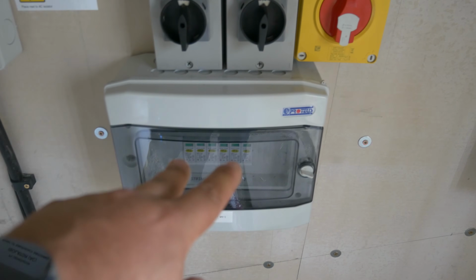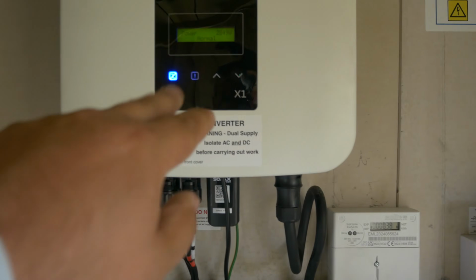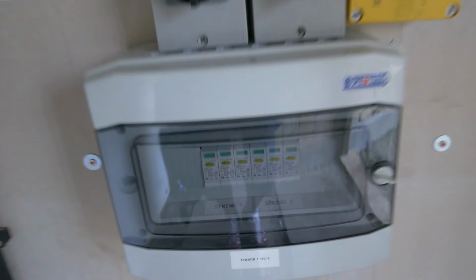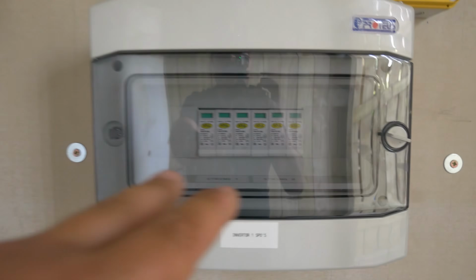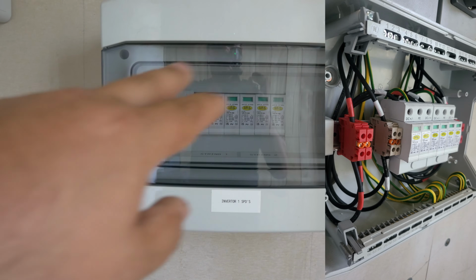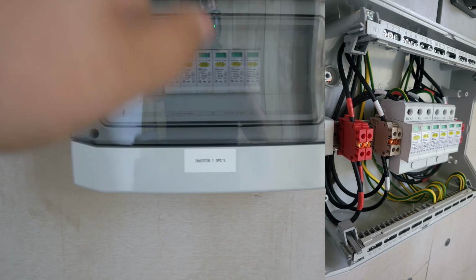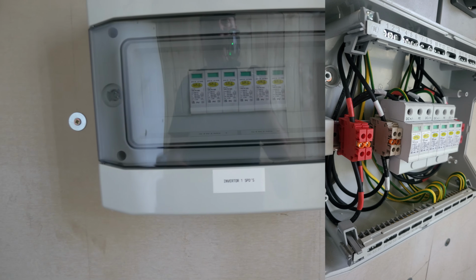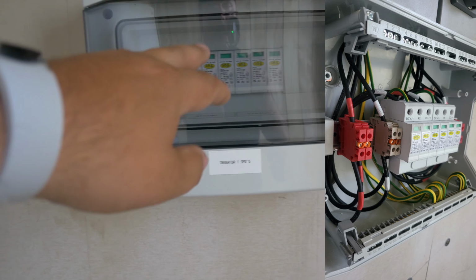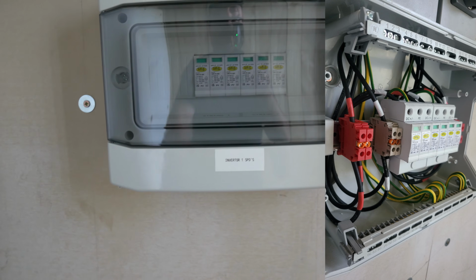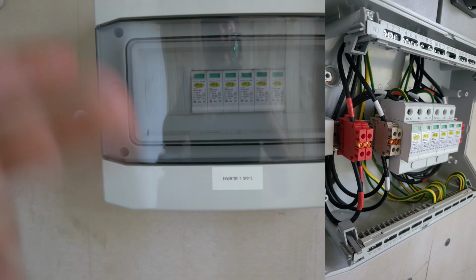If we isolate the power, it kills power off to the SPDs and also up to the inverter. We've got an SPD here on each string, and as I showed during the testing, these have points to one side where you can disconnect a little terminal bar, so the SPDs are taken out of the test sequence for your insulation resistance testing - because if you were testing with those links in, they'll drop all your current to earth, since that's what they're supposed to do, and give you a failed result.